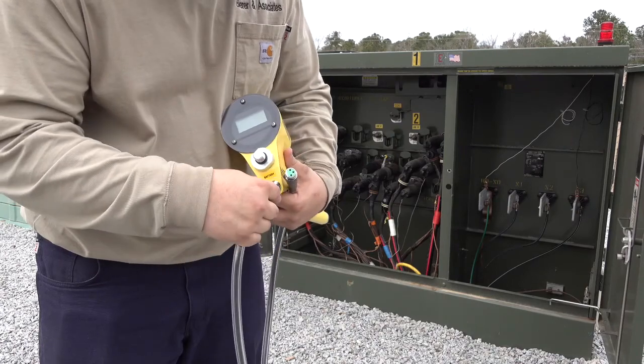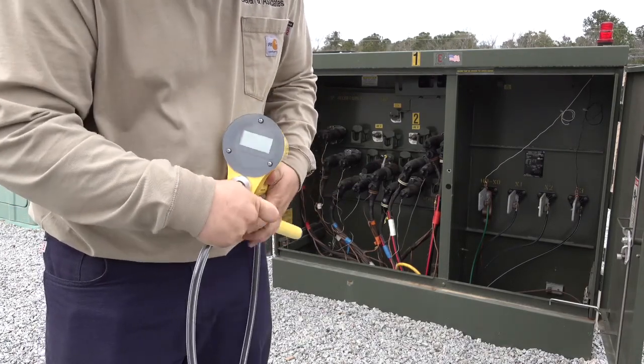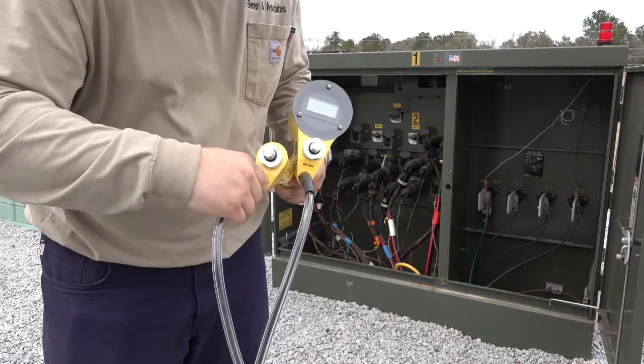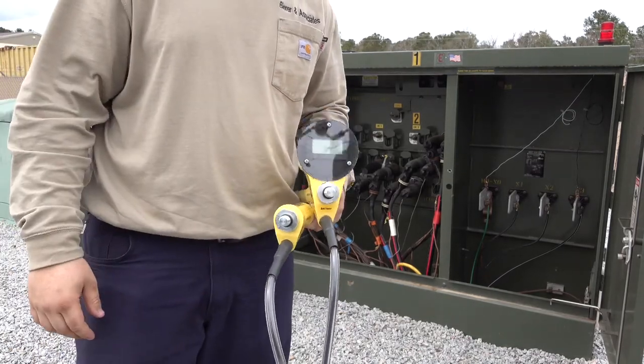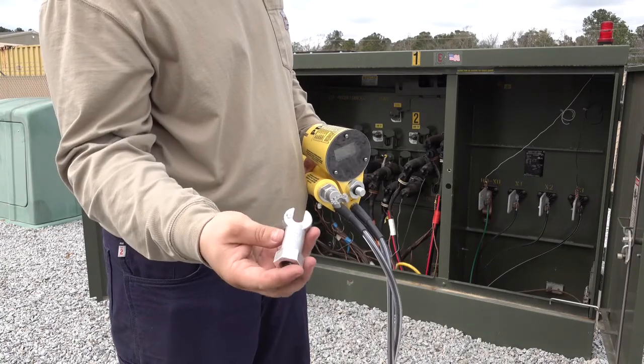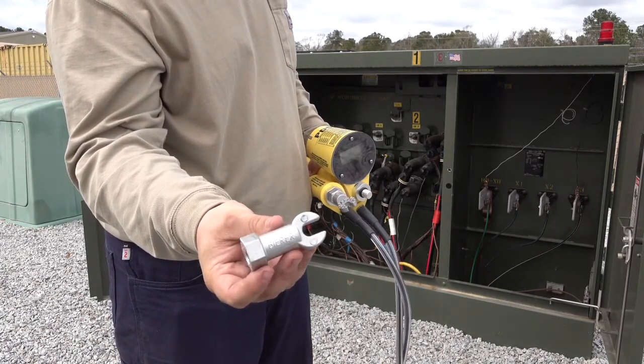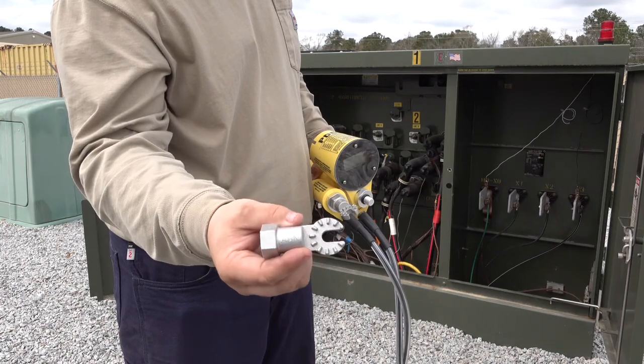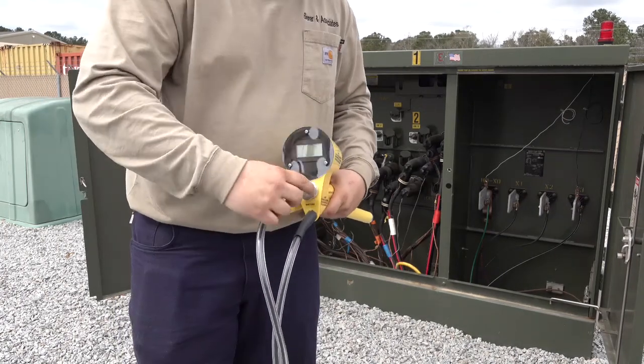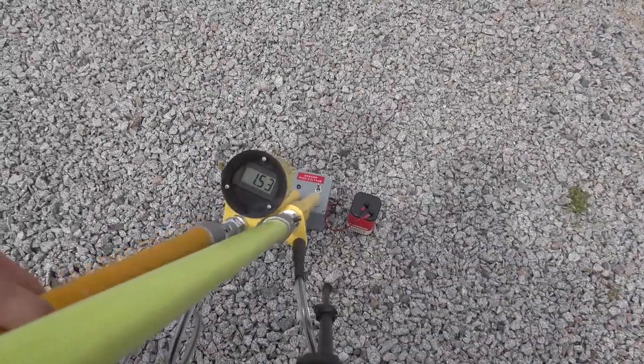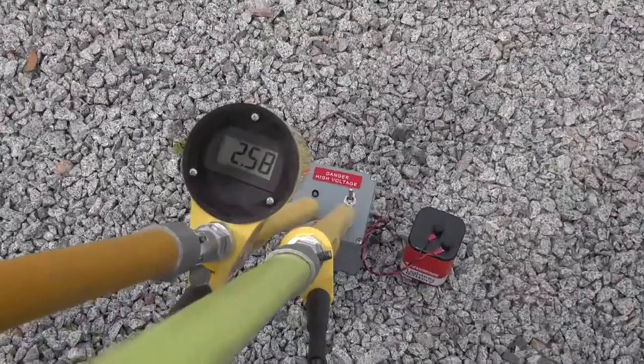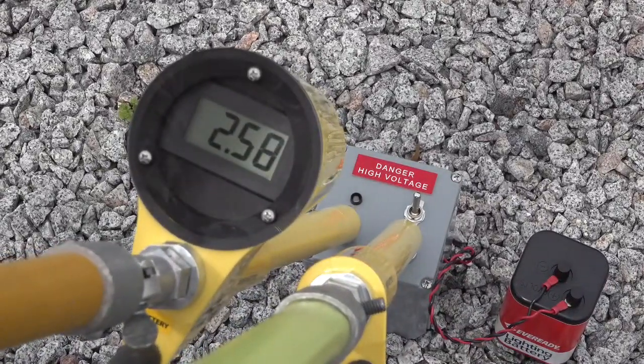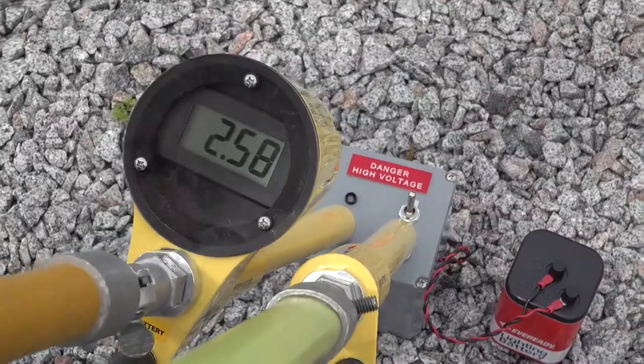After the self-test, connect the interconnect cable and attach the live-line tool adapters. In this demonstration, we're using our Bierer universal stick adapters so we can perform what's called a known voltage test. We're using the Bierer 3 kV power supply, which will test the meter probe circuitry, the interconnect cable, and the second probe for a complete and extremely safe 100% high potential test.